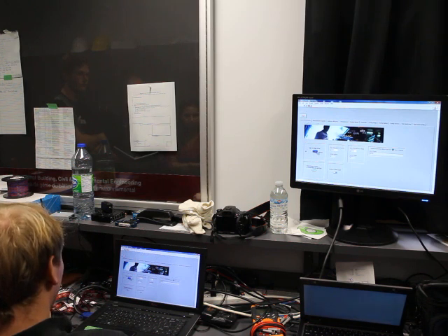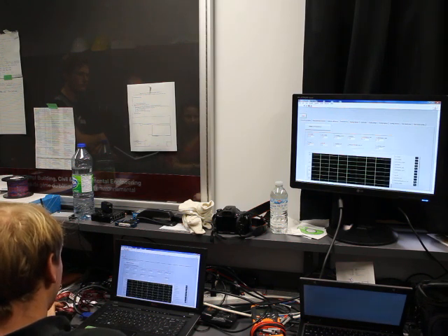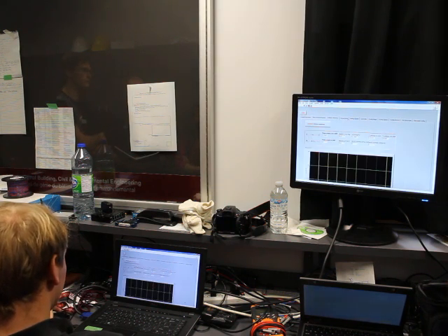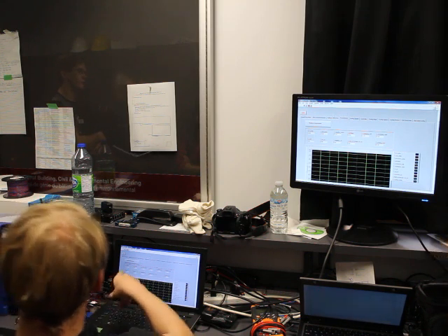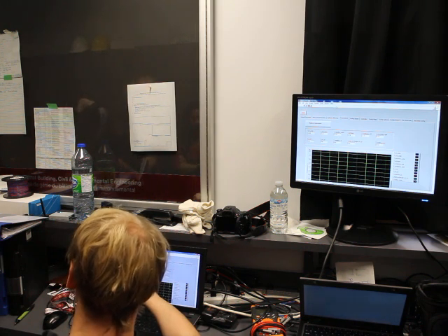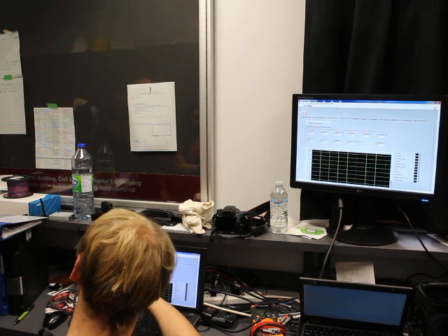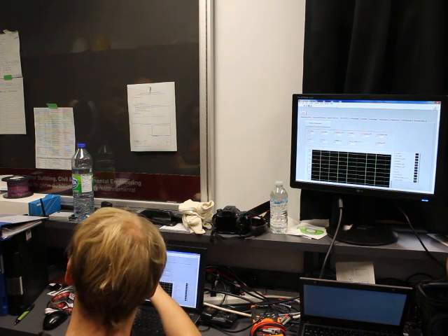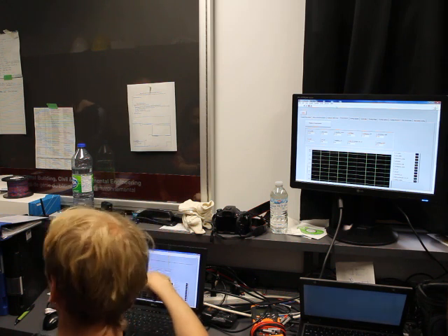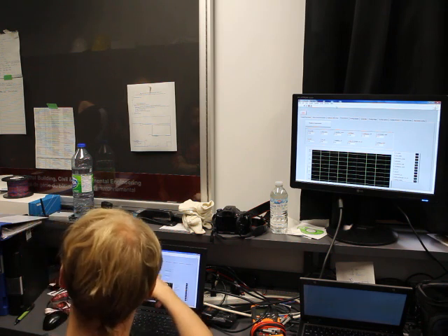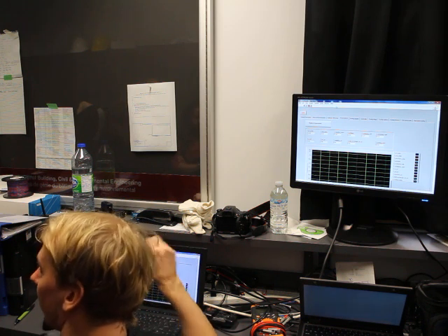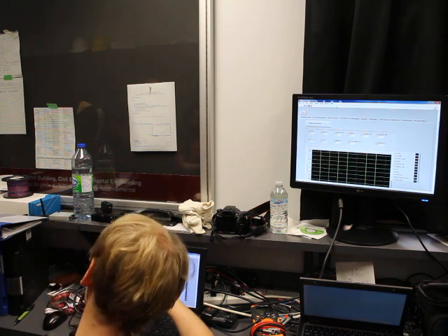Okay. Then maybe we go first to the temperatures. What we can see already: the inlet of the collector is at the moment at 22.84, outlet is 43, mass flow is 45, ambient is 22. Ventilation left is the left one of the ventilation system, the right one is 21. And the cooling water, which is going to the temperature control unit, is at 10 degrees C.